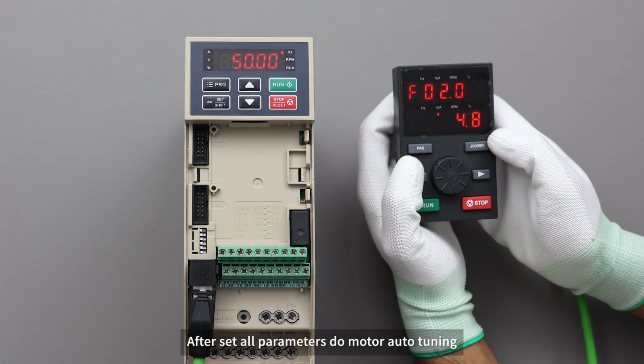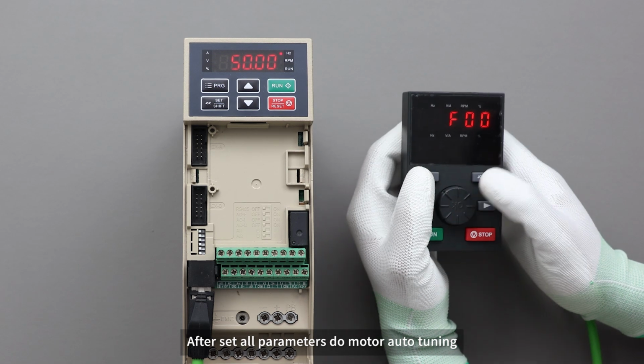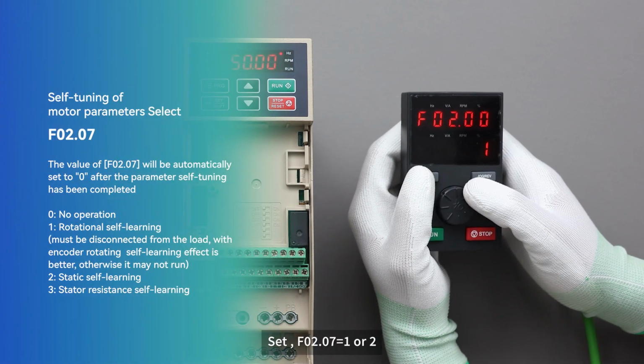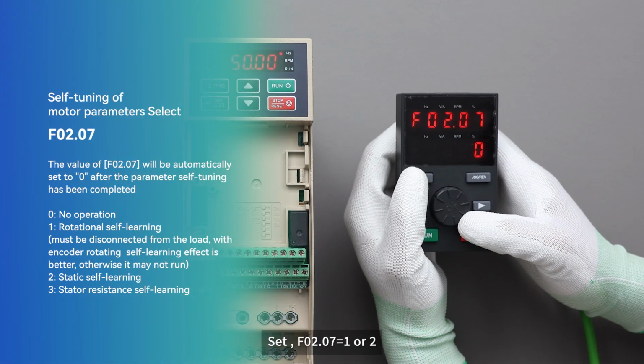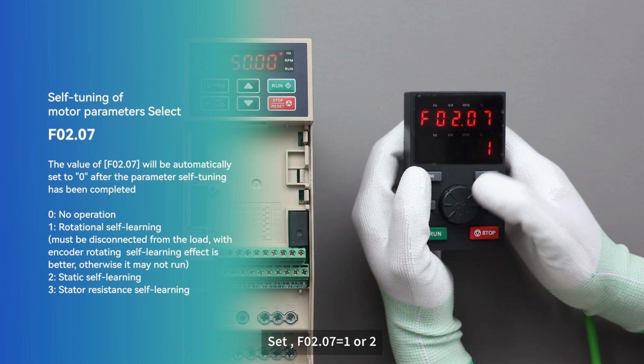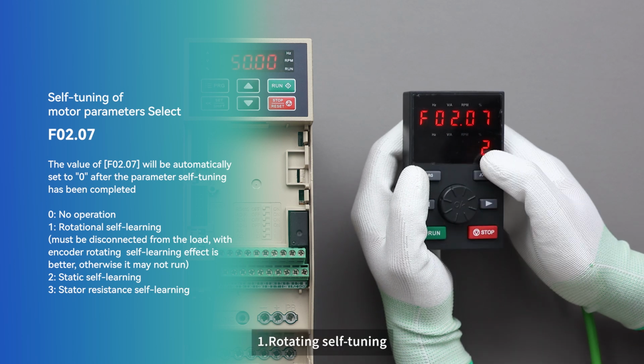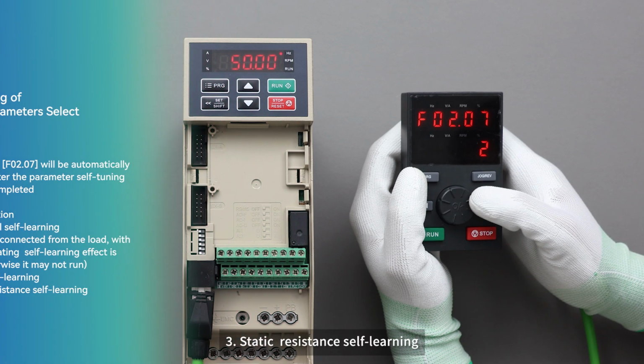After setting all parameters, do motor auto tuning. Set F02.07 to 1 or 2. 1 means rotating self-tuning, must be disconnected from the load. 2 means static self-tuning. 3 means stator resistance self-tuning.